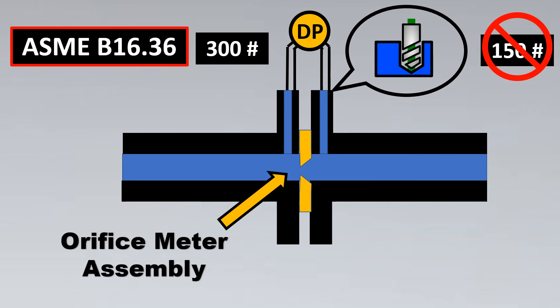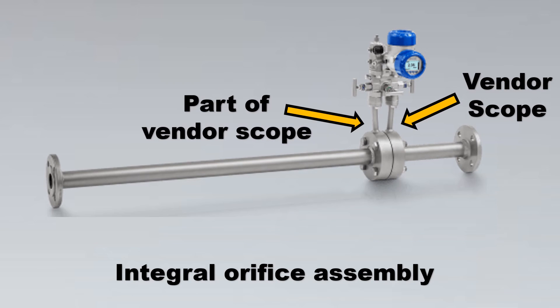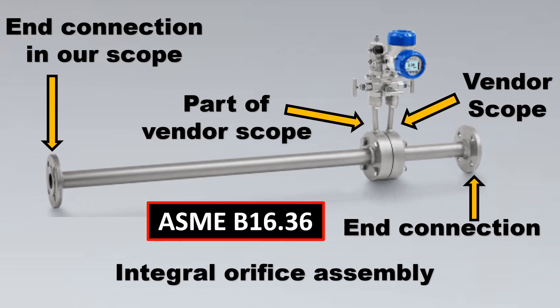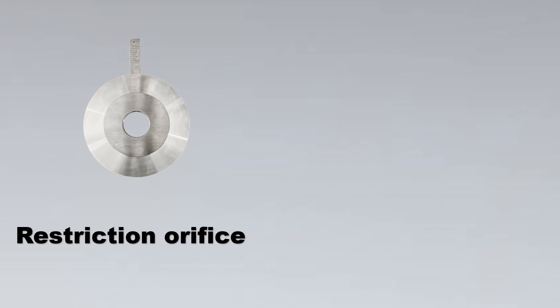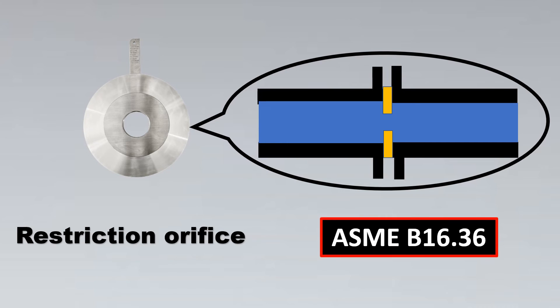For an integral orifice assembly, these are part of the vendor scope, and the end connections provided have no holes drilled into them. So there is no need to specify ASME B16.36 for integral orifice meters. Similarly, a restriction orifice simply puts a restriction in the line of flow with no differential pressure to be measured, so the flanges don't have to be drilled — and hence we don't need ASME B16.36 for restriction orifices either.